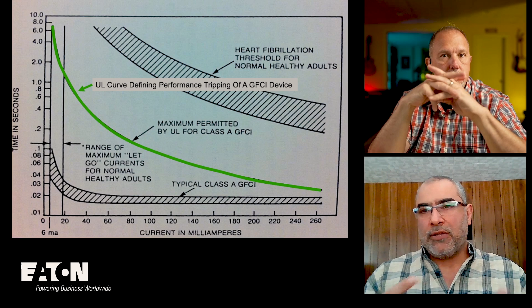So, and Tom, to your point, the green curve that you're showing, this is the UL curve, Class A, plus special purpose as well, plus C, D, and E for that matter. But this curve is the maximum amount of time, or the maximum exposure time, allowed by UL. So you can trip anywhere underneath this curve. That's why you're showing this typical curve, which obviously is a constant time. And this is what most of the Class A GFCIs that we purchase from like Home Depot and install at home, they don't have a curve. It's just like once you detect the 6 milliamp, you trip with a certain time delay.